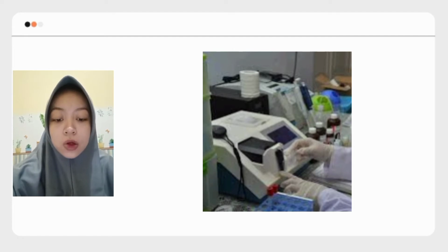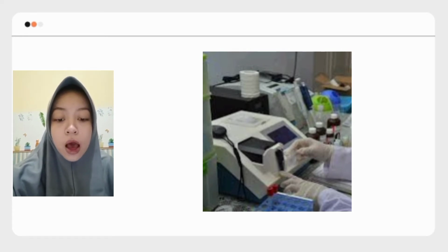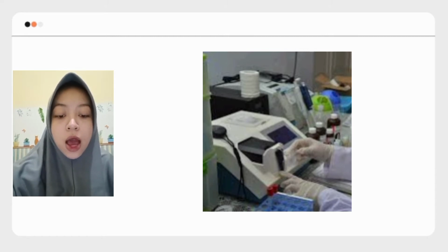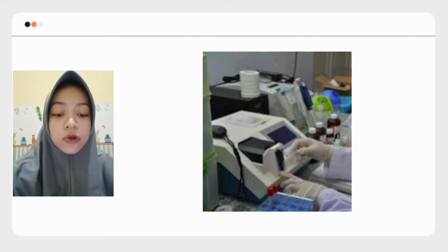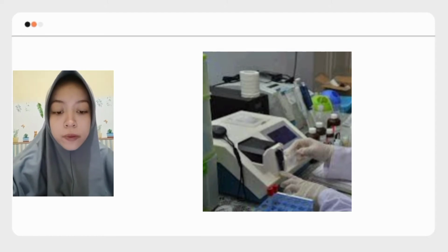If the test results show abnormally high or low values, the test must be repeated to confirm the result in the following way. Blood glucose level of more than 16 millimoles: dilute the solution with aquades as much as the volume used. Enter the diluted solution B in the cuvette. Position the needle at 0. To get the blood glucose level, the result is multiplied by 2.